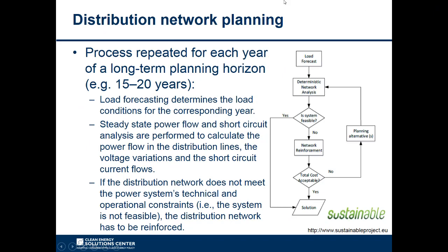Distribution network planning is very important when looking at the evolution of the system, so the distribution companies need to do a proper planning for the future scenarios. Normally, they look at horizons of between 15 and 20 years, and they need to decide what kind of investments they are going to do in order to meet the demands they have, both the expected load, and also respect the quality of the power they are supplying.